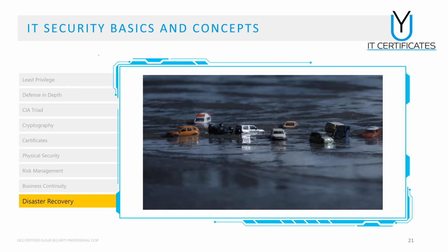At that time, most of the ISPs' infrastructure was down because most of them had their power generators in the basement. All the basements were flooded and the power was cut, and we were not able to run the data centers. All the data centers were idle, and all the services were down, and we spent about a week until the services were retrieved. And this was the concept of disaster recovery.